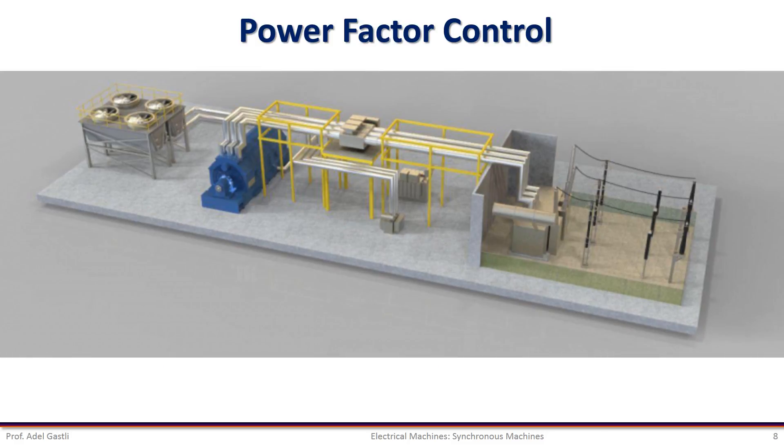If a synchronous machine is not transferring any power, but is simply floating on the infinite bus, the power factor is zero. That is, the stator current either leads or lags the stator voltage by 90 degrees. The magnitude of the stator current changes as the field current is changed, but the stator current is always reactive.